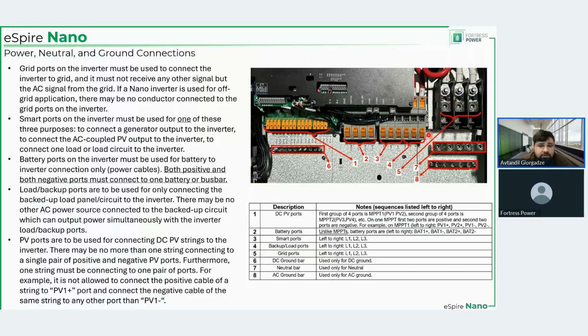So yeah, this is what I was showing. You have L1, L2, L3 for load, L1, L2, L3 for smart port, may that be generator, AC coupled PV or load. These 2 plus 2, these are 4 ports, 2 positives and 2 negatives, and L1, L2, and L3. That's grid. So yeah, no 4 ports for AC anywhere. And as I said, neutral and ground are here. And we stop sharing.